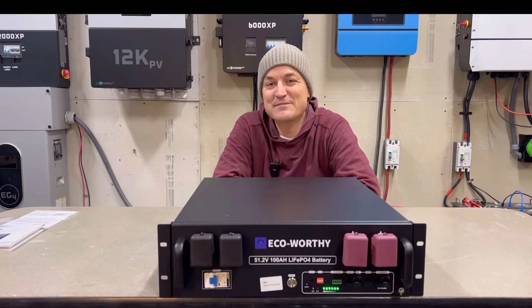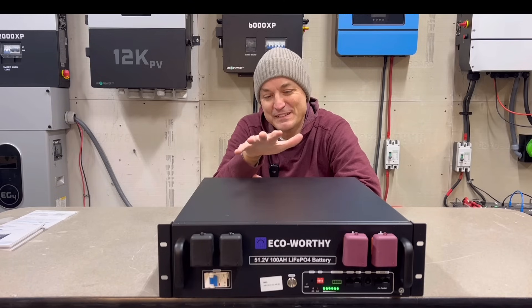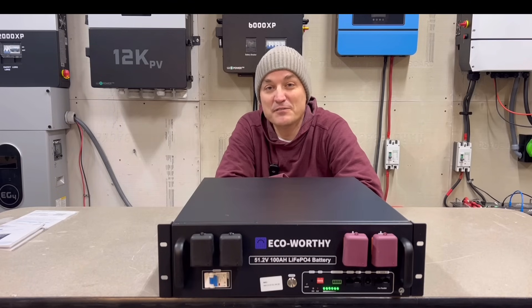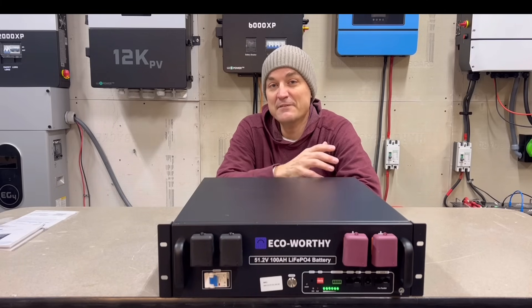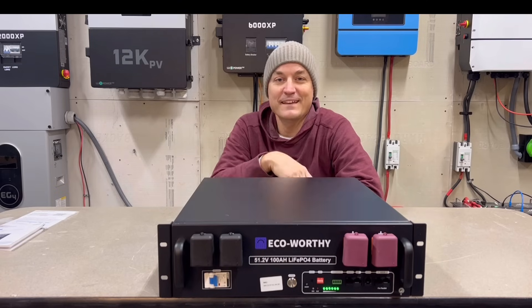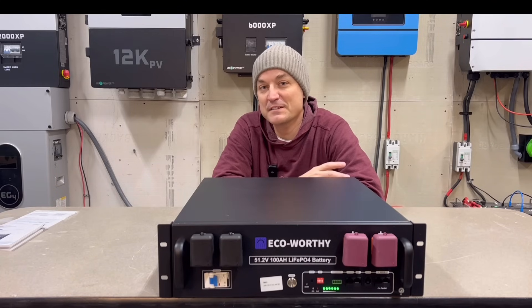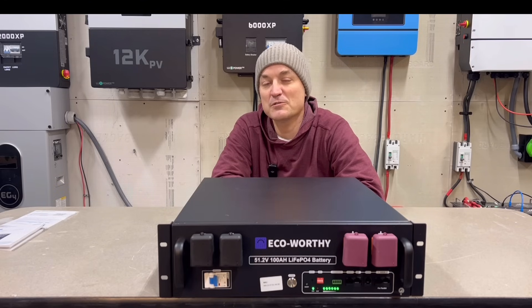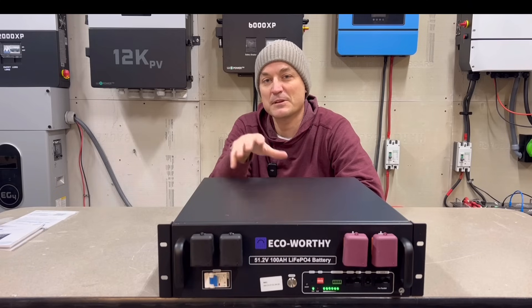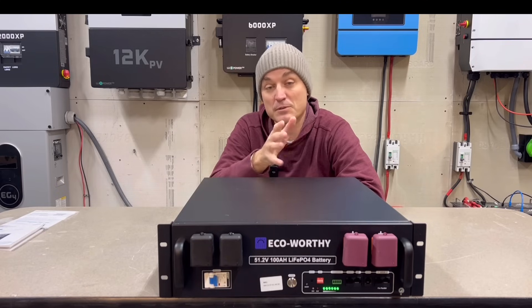To finish up: I really can't believe the price point this battery is at. In the past, if you wanted a really cheap battery, you often had to sacrifice build quality or communication. But this battery has RS-485 and CAN communication, and it didn't have any issue communicating with the 12,000 XP. A lot of the newer inverters communicate via Pylontech, and that is something this battery uses — most newer EG4 inverters, Solark, and others. You may not be able to communicate with some versions of Growatt inverters or some Voltronic, so it really depends on the inverter. You could always contact EcoWorthy to make sure your make and model will communicate with it.